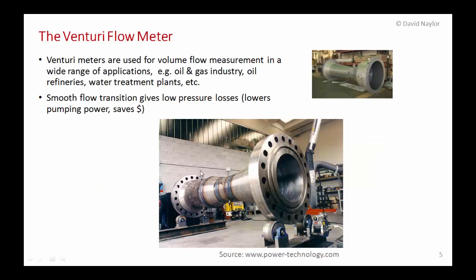Venturi flow meters are used in industry for measuring volume flow rates across a wide range of applications — the oil and gas industry, oil refineries, and water treatment plants. As you can see from the photo, they can be used for very large pipelines. The big advantage of a Venturi flow meter is that it has a very smooth flow transition, which results in very low losses, low turbulence, and very low pressure drops. That results in lower pumping power, saving money in the long run even though the device is more complex.